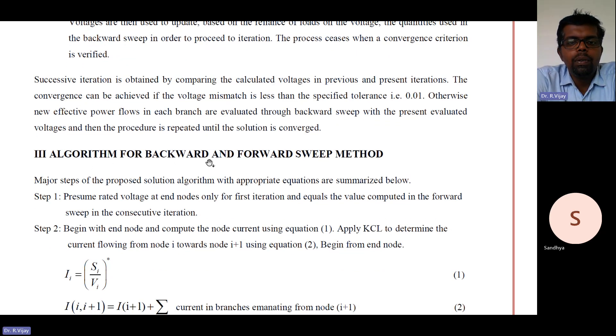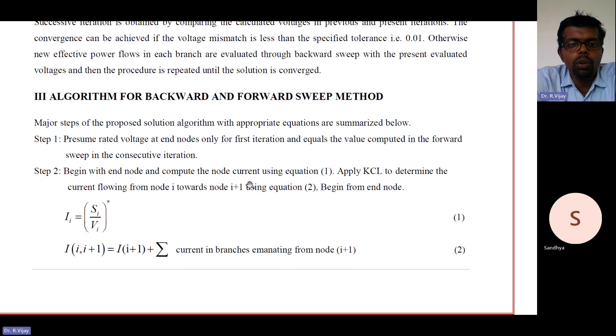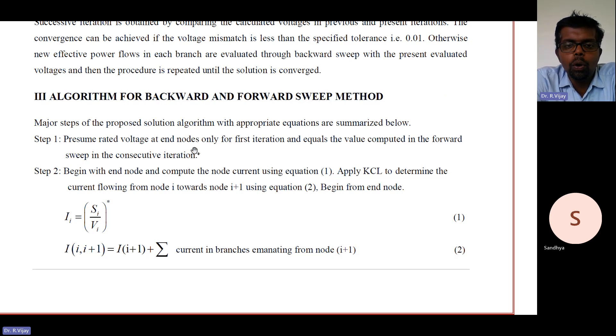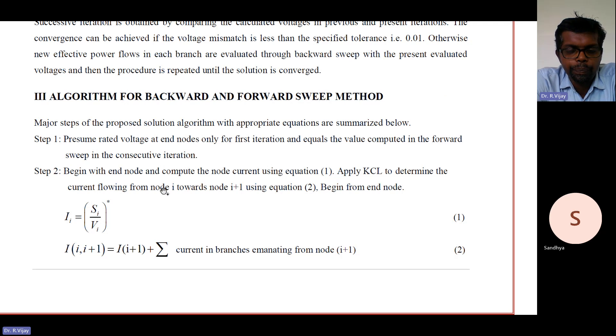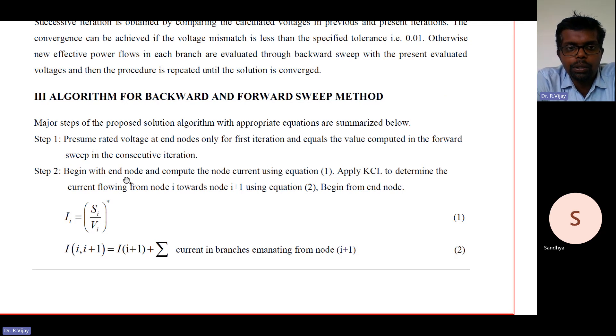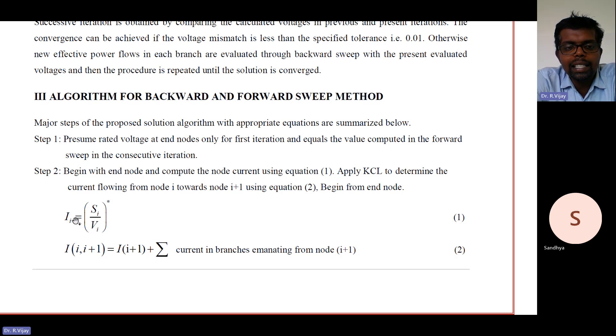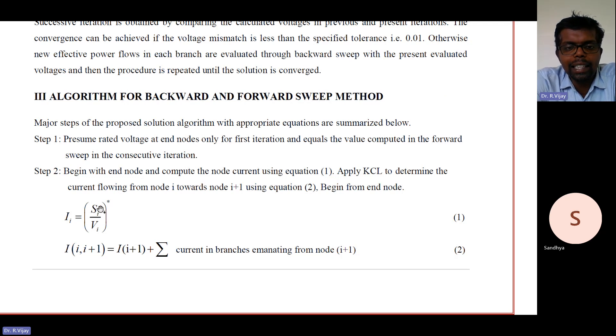Coming to the algorithm for the backward and forward sweep method, the major steps are summarized below. Step 1: Assume rated voltage at each node for the first iteration, equal to the value computed in the forward sweep in consecutive iterations. Step 2 (backward sweep): Begin with each end node and compute the node current using equation 1 — that is Iₐ = (Sᵢ / V)*, where Sᵢ = P + jQ, the apparent power. The star denotes the conjugate.